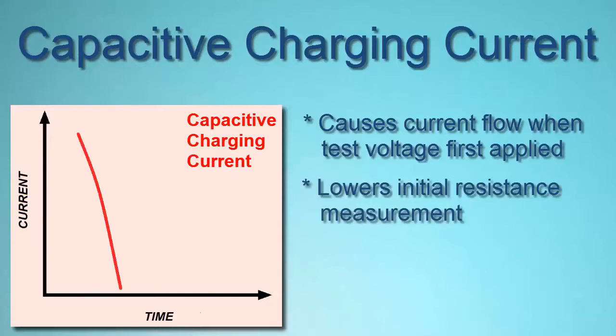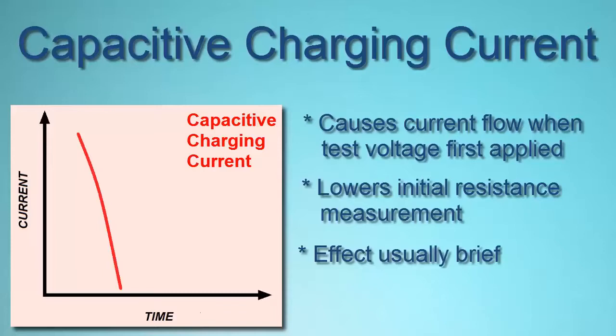This effect is usually brief, often lasting less than a second, although in very long cables or large motors this can last much longer — up to 30 minutes or more. Capacitive charging current is not an indicator of insulation quality, but it needs to be accounted for to ensure your measurement is meaningful and relevant.